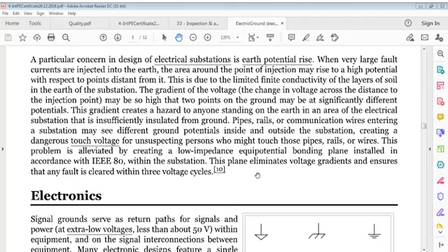Earth potential rise. When very large fault currents are injected into earth, the area around the point of injection may rise to a high potential with respect to points distant from it. This is due to the limited finite conductivity of layers of soil in the earth of the substation.